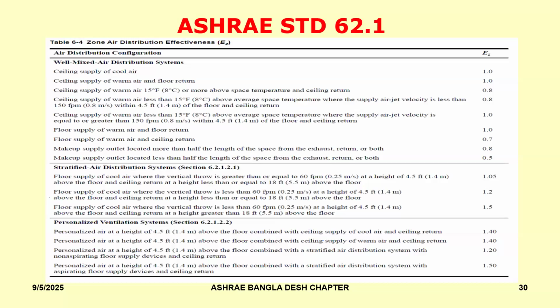So can we get it higher than 1? Of course you can. That is, if you use distribution systems like the stratified air distribution system, which is shown over here. You can see that you can achieve as much as 1.2 or 1.5 simply by choosing the kind of air distribution system that you would like to employ. For example, we have systems like displacement ventilation, or underfloor air distribution, which can yield numbers of 1.2 to 1.4 very comfortably if they are well designed and put into operation.